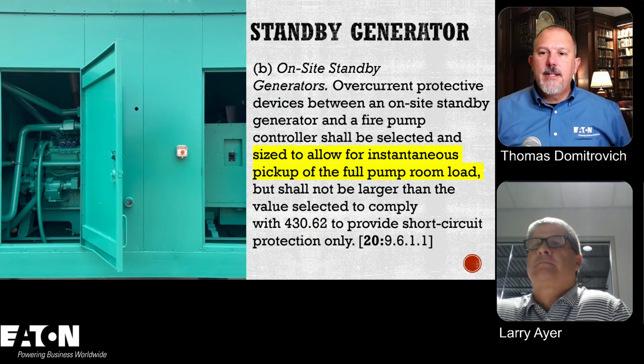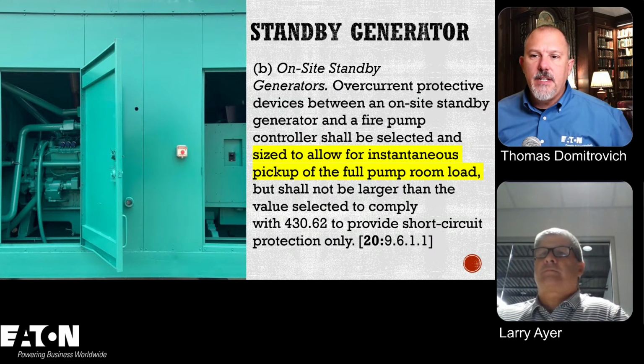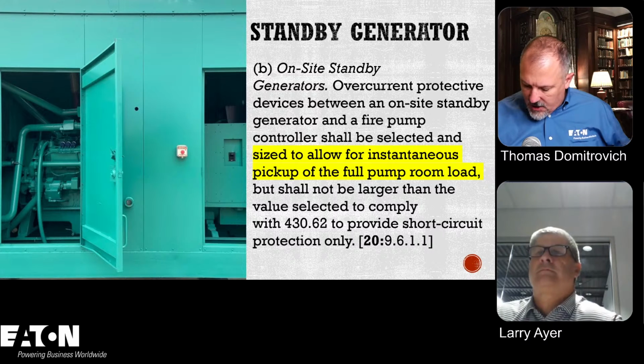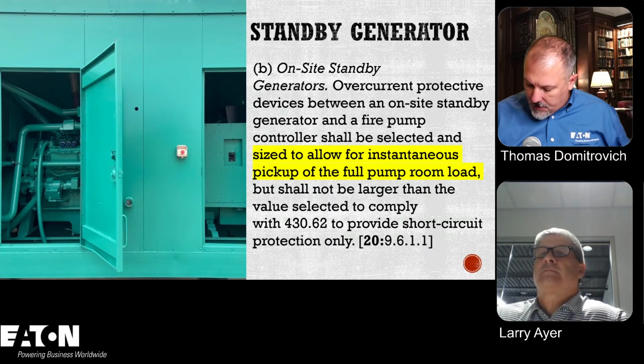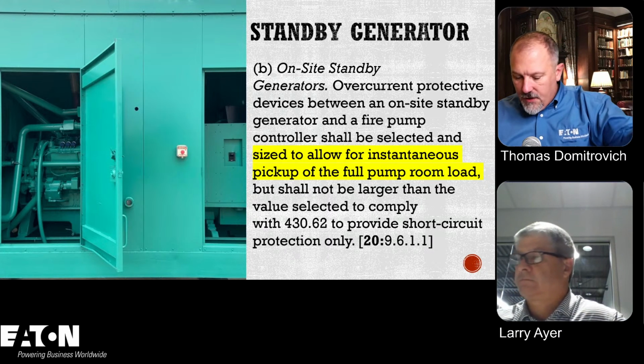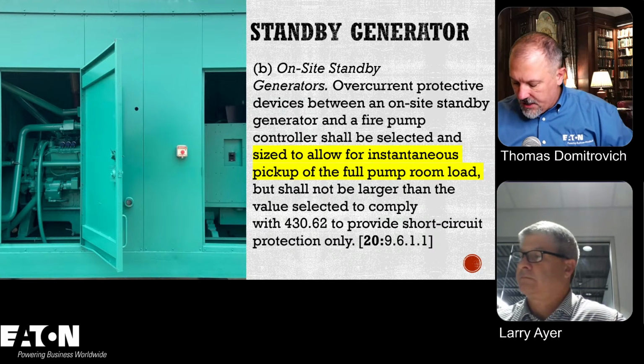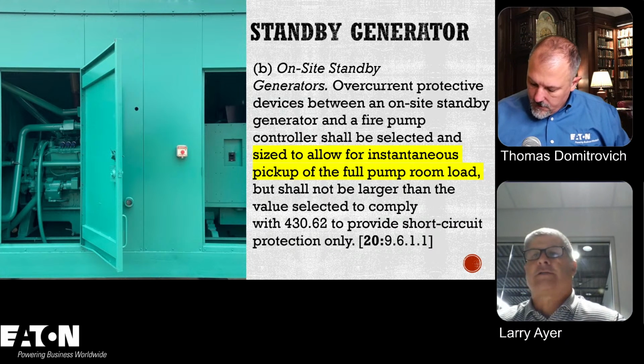Standby generator, on-site standby generators, overcurrent protective devices between. Okay, so this is the C option. This is that on-site, that's the B option. We hit individual sources. Now we're hitting on-site standby generators. Correct. And so this is the key.